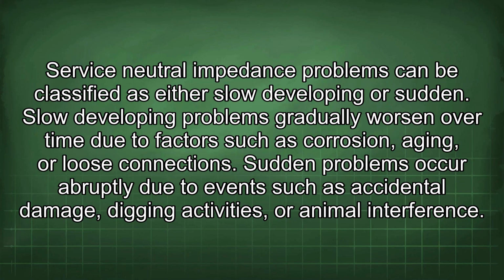Service-neutral impedance problems can be classified as either slow-developing or sudden. Slow-developing problems gradually worsen over time due to factors such as corrosion, aging, or loose connections. Sudden problems occur abruptly due to events such as accidental damage, digging activities, or animal interference.